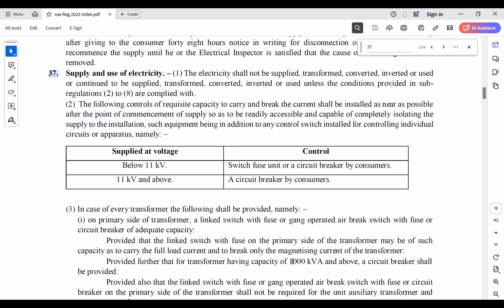Now, after this new regulation, there are a lot of issues that have come up while working on field. I will try to explain it in a case by case manner. Number one thing I would like to point out is that this high tension power supply, HT supply, where the 11, 22, 33 kV voltage level comes into force, starts from 50 kilowatt onwards in various states. For example, if you speak about Maharashtra, they have a mandate wherein above 200 kilowatt you have to go for HT supply, up to 200 kilowatt LT supply can be given.